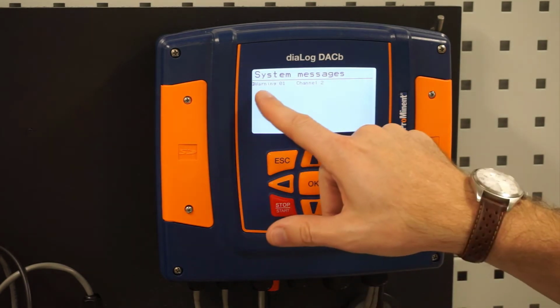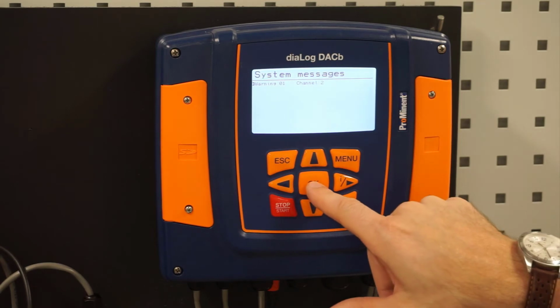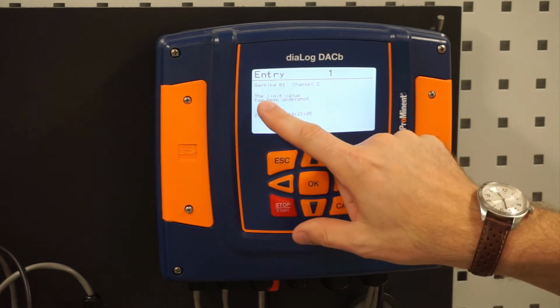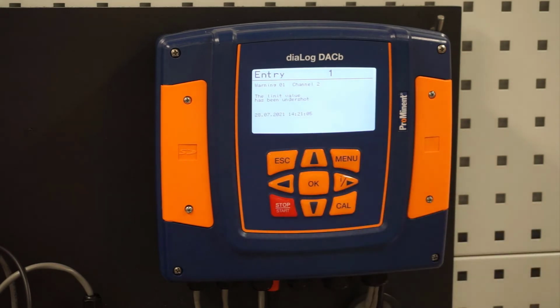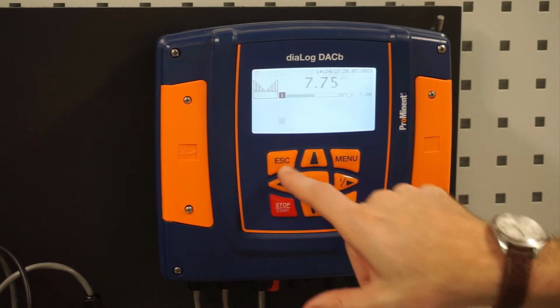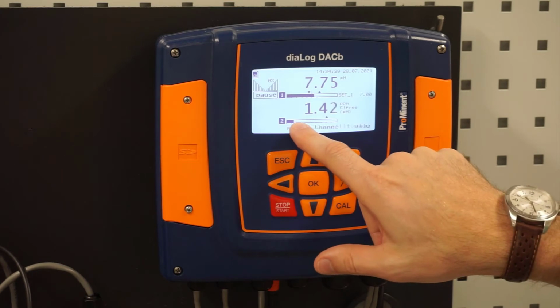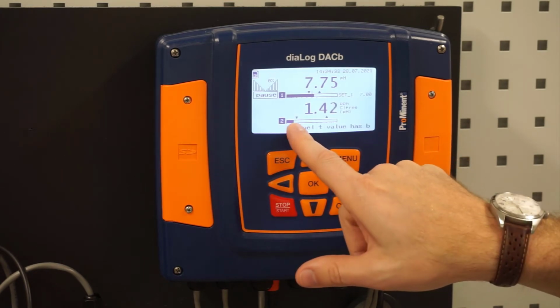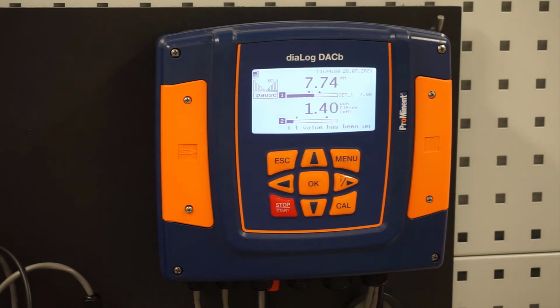I can click on it. You can see it's warning 1 on channel 2. If I hit OK, it tells me that my limit on channel 2 has been undershot. And if I back out, I agree with that. My lower limit is higher than what my black bar is. So that's what that is. I'll show you how to adjust those limits, or if you prefer to turn them off completely. With them on, I can actually send a signal out to somebody and let them know, hey, we hit a low limit. You may want to come down and look at maybe our chlorine pump has run out of chemical.